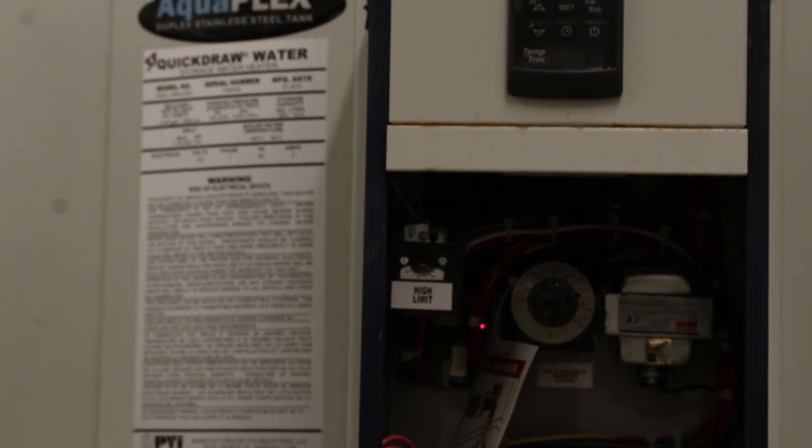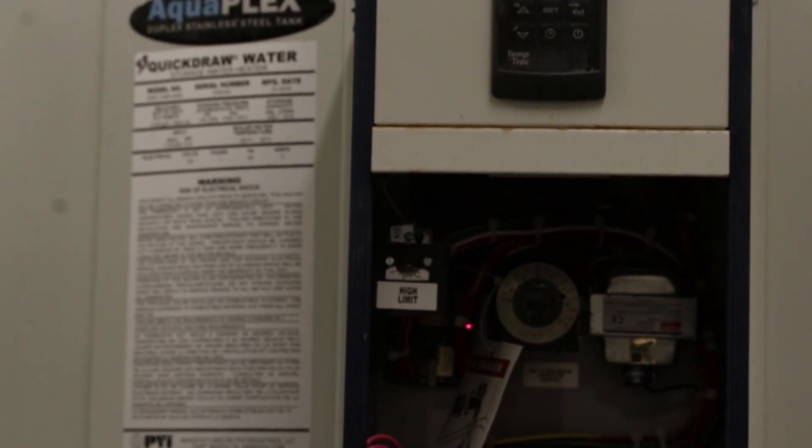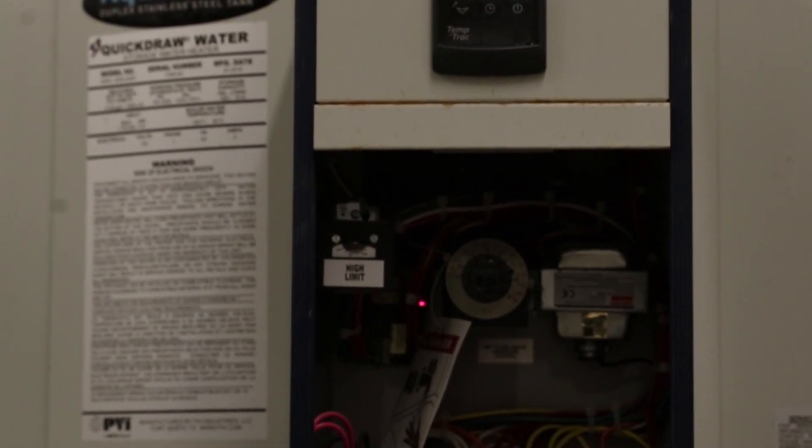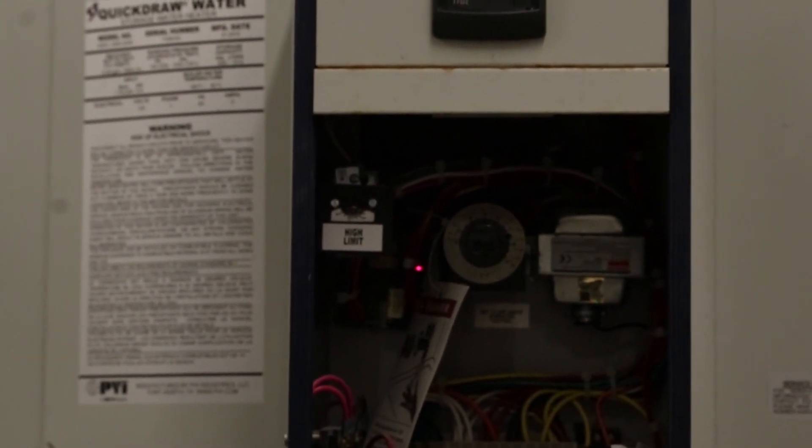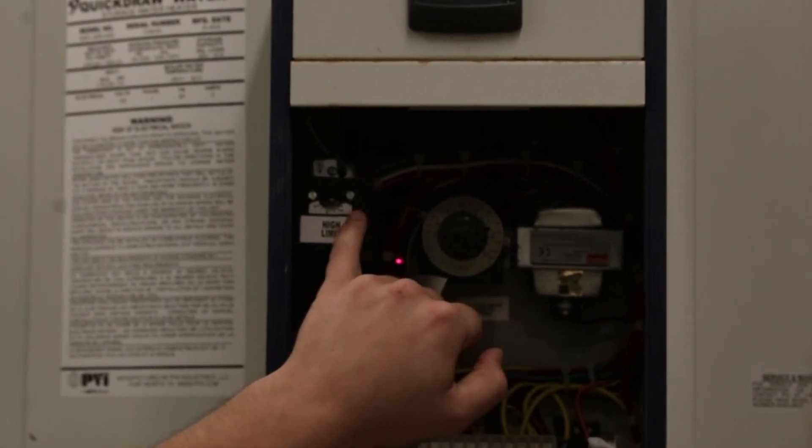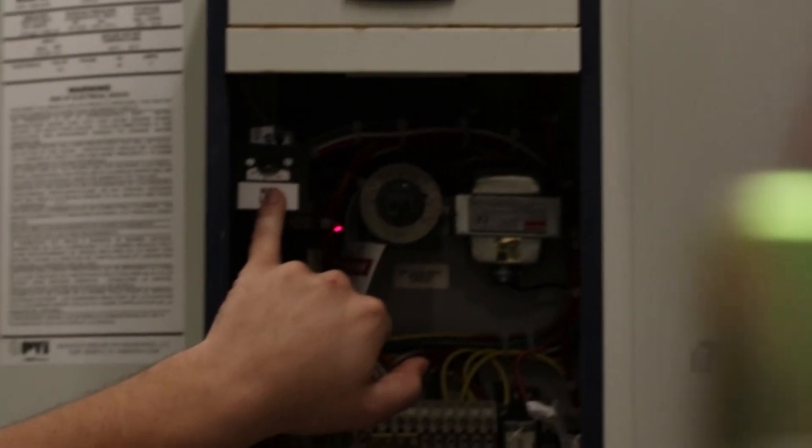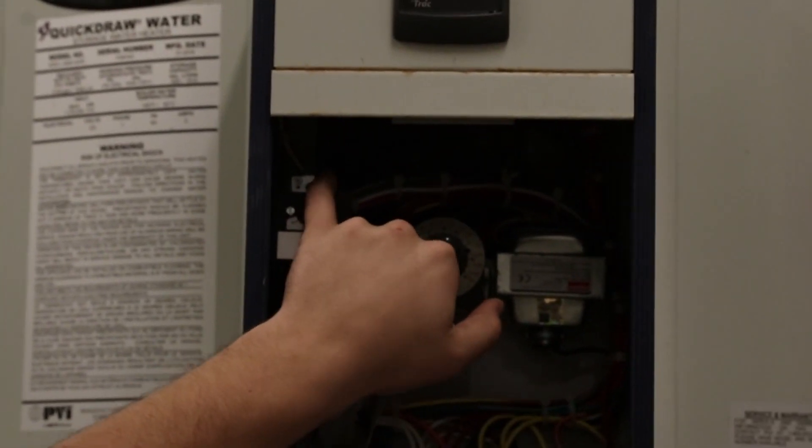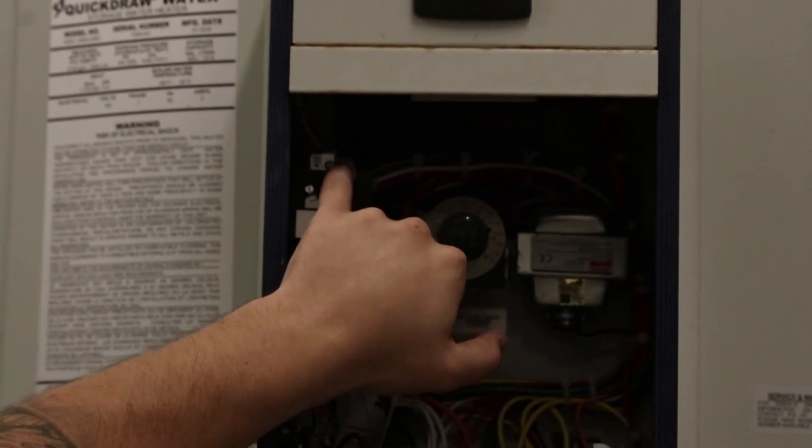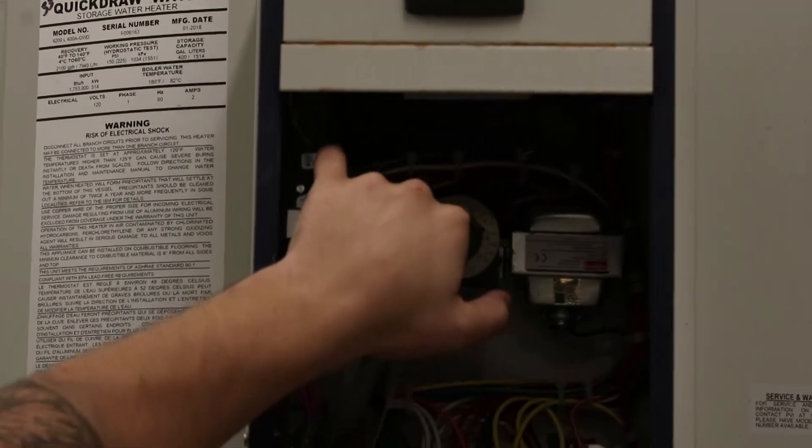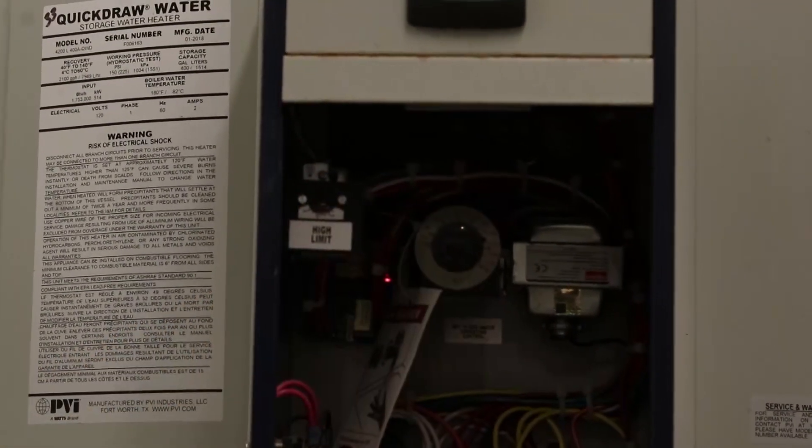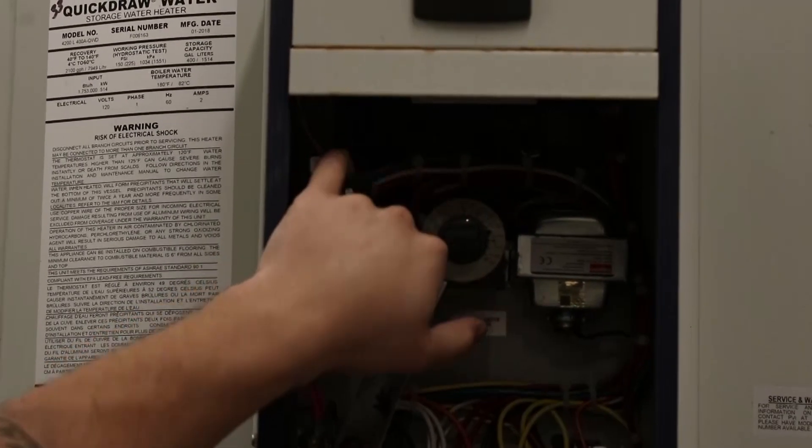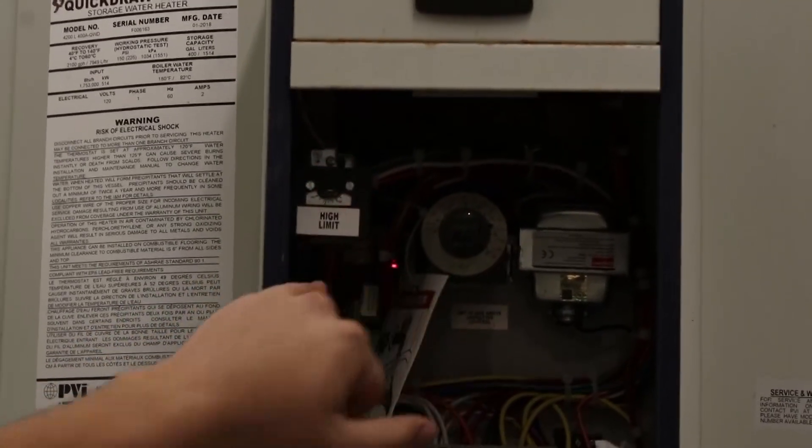If there's any type of malfunction of any of the controls or components that will cause this water heater to overheat the water in the tank, then this control will trip. It's a manual reset type, so it will not allow the water heater to operate again until someone comes in and presses this button. It's a green button there. Right now, there's no resistance on the button. It doesn't click because the control is not tripped. If it is tripped, you'll press this button, you'll get a click, and the control will reset.